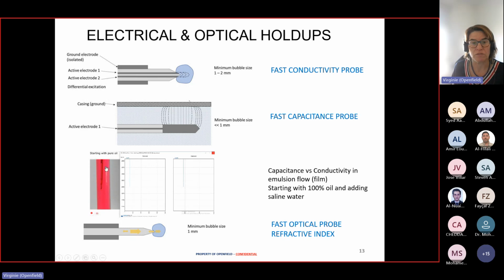I can replay. So we're starting with oil. We can see 100% oil. We can see the probe. And as we are adding water and it's going very high in this flow loop, you start to not see the probe. That's because it starts to be like a mayonnaise, let's say. You see mostly oil and then some little water droplets. And the electrical level, the conductivity level, stays flat and low. And as we're adding water to the system, the capacitance is detecting. So that's what we see also in the field, that when we combine these two in oil emulsion, the conductivity or resistivity probe, similar problem, will not detect the water in oil emulsion.